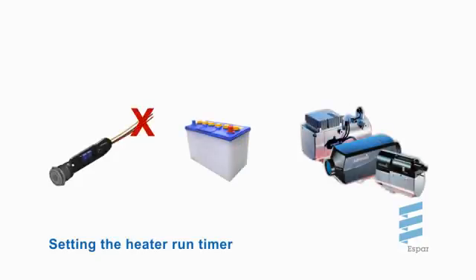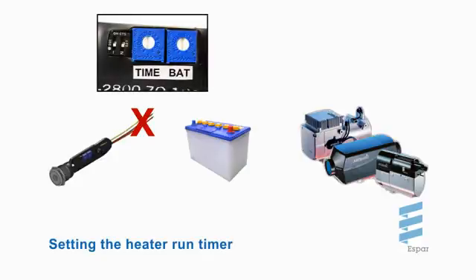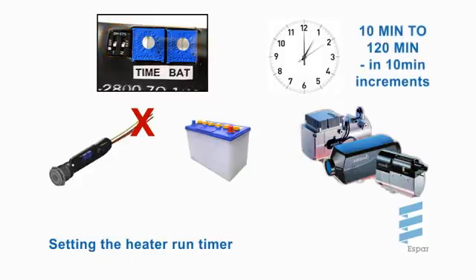The heater run timer can be preset by turning the potentiometer labeled time. The heater run time preset will be read in minutes when the dip switch number one is in the down position. The minimum setting is 10 minutes and the maximum setting is 120 minutes in 10 minute increments.